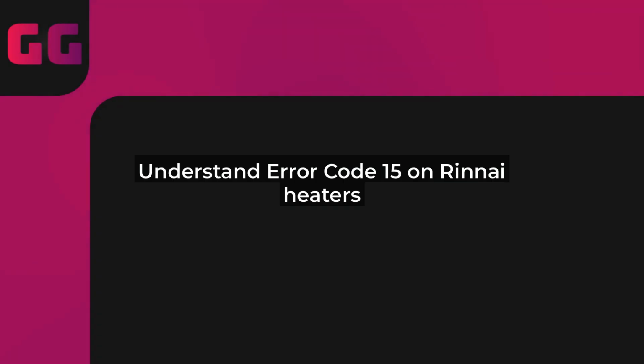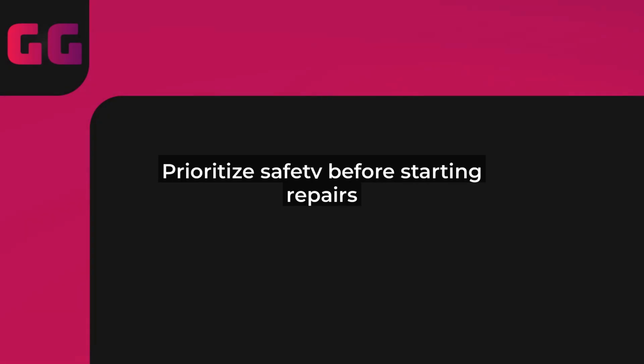This error typically signals a problem with the flame detection or ignition system, which can be caused by issues like a faulty gas supply, dirty sensors, or even a simple reset. In this video, we'll go through a step-by-step guide to troubleshoot and fix it yourself, saving you time and money. But remember, safety first. Always turn off the power and gas before starting any work.